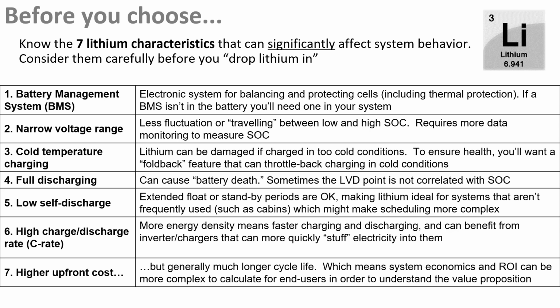However, you do want to make sure that you have accurate monitoring for the state of charge. You're doing either true shunt measurement, or it's being calculated internally by the battery management system, where you can visually see the battery's state of charge in terms of a percentage of capacity. Just utilizing voltage is not going to be very accurate, as you can have the same battery voltage at 80% state of charge as at 20% state of charge, and you wouldn't know any better in terms of using the voltage measurement to correlate that to how much energy is actually stored in the battery.